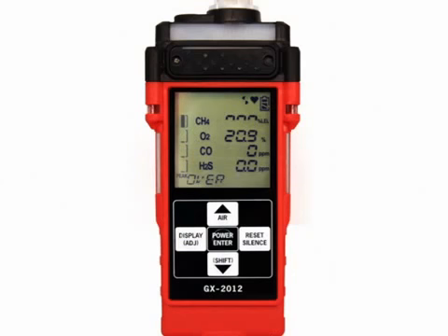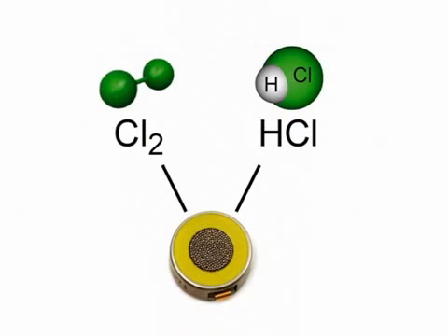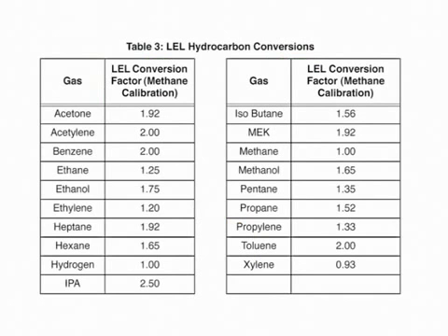When this happens, over is displayed below the gas list, and the display units to the right of the combustible gas channel change to percent volume. Silicone vapors and chlorine and fluorine compounds, such as chlorinated hydrocarbons, can damage the percent LEL sensor. These compounds should be avoided. If exposure to these compounds is suspected, verify the percent LEL response on a known gas sample.